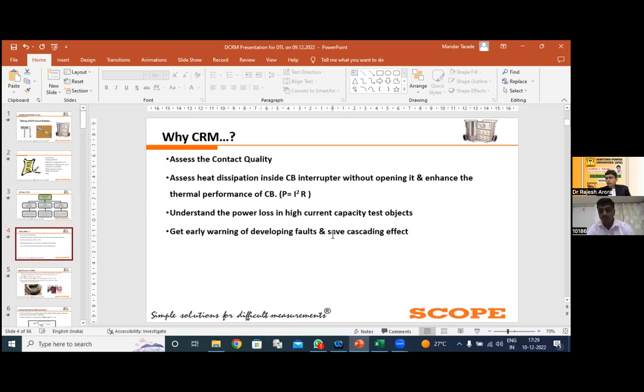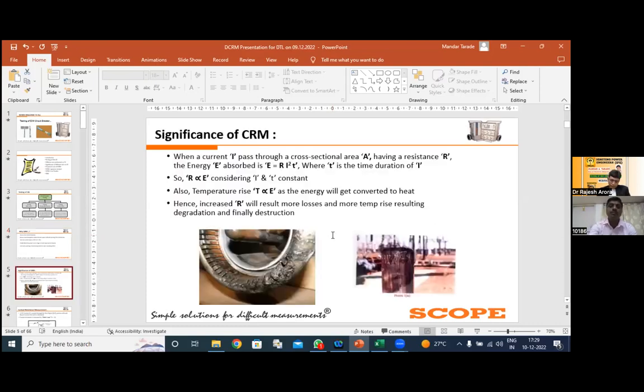If there is a significant rise in the value of the contact resistance, then as per the standard, the contact resistance value should not exceed 100 micro ohm. If it is exceeding that limit, then we need to take corrective action. So with the help of this, we are able to identify the issues.